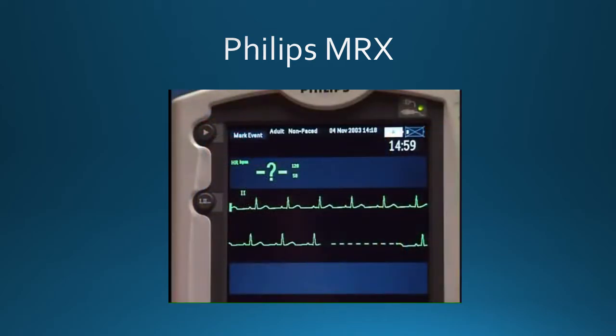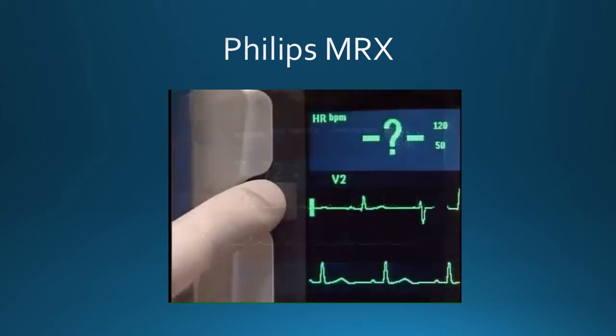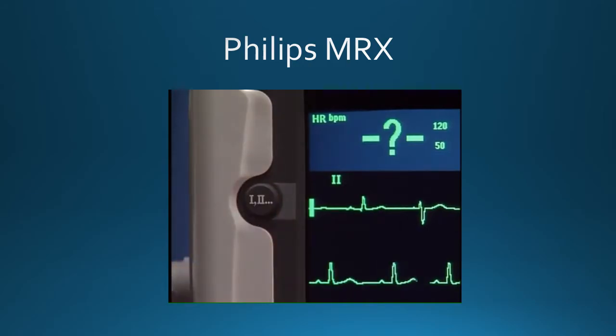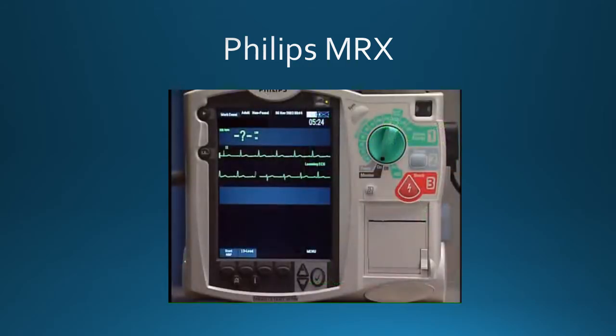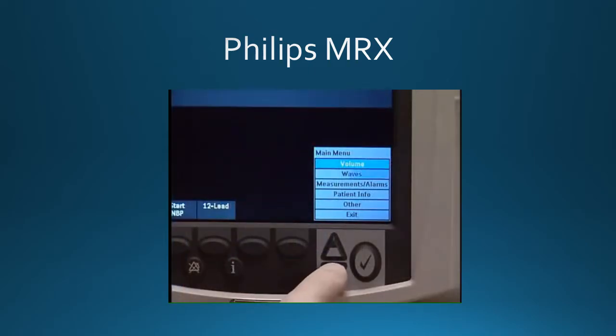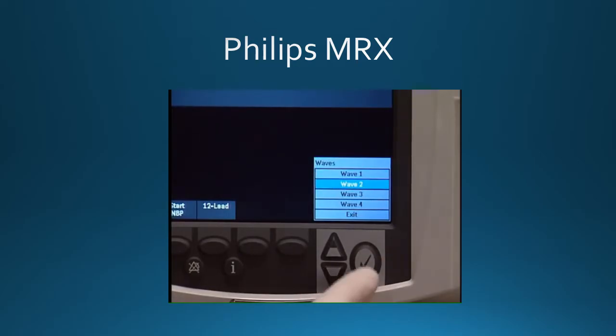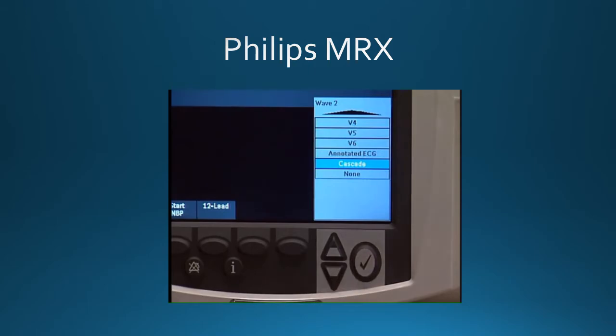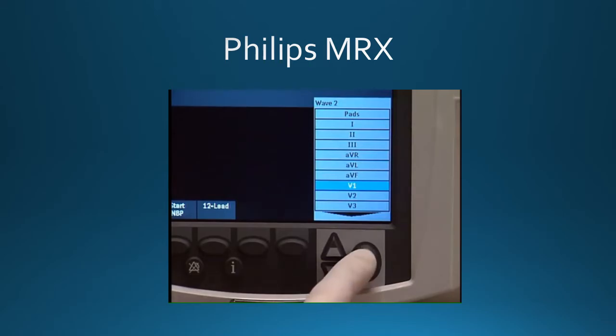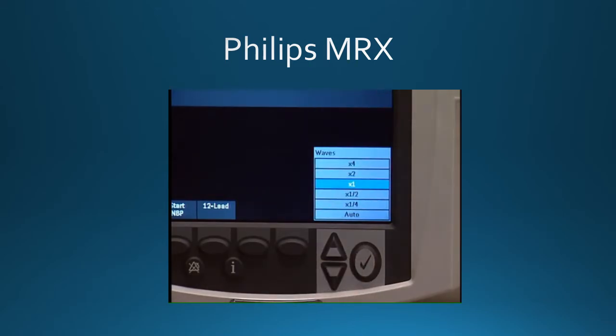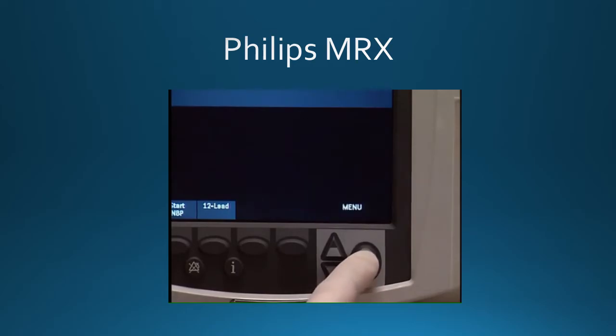The monitoring leads available depend on what type of ECG cable is connected to the MRX. Press the Lead Select button to display the desired lead in wave sector 1. To change the waveform displayed in wave sector 2, 3, or 4, press the Menu Select button, navigate to Waves, select the desired wave, and press Menu Select again. Select the desired lead. And finally, choose the preferred wave size and press Menu Select again.